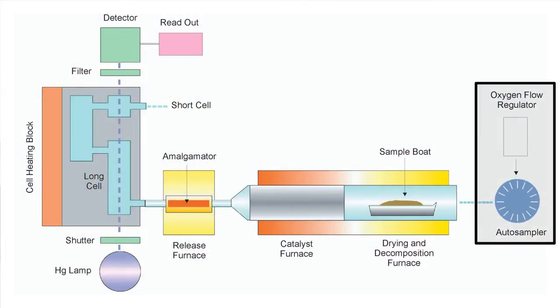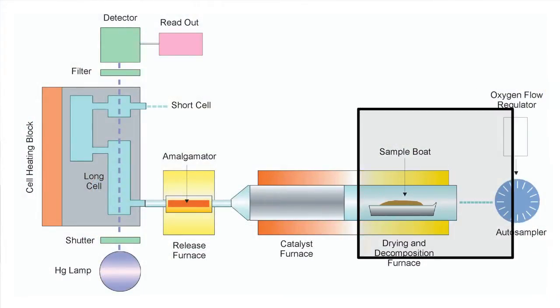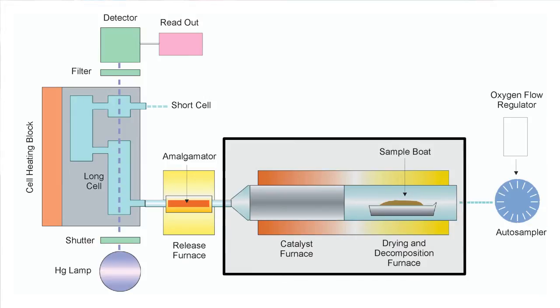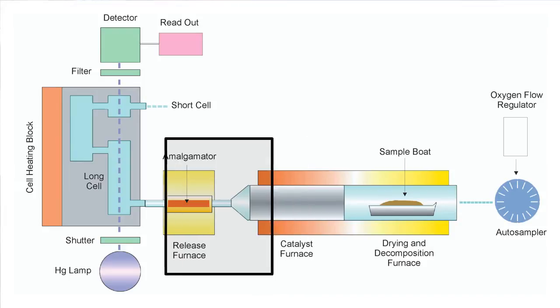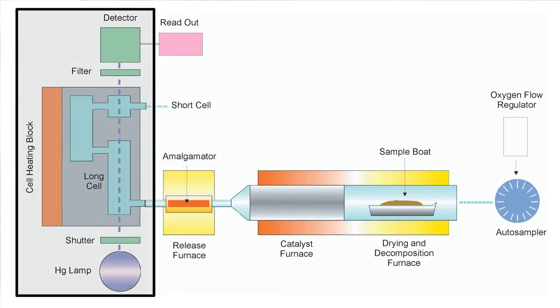The decomposition products are carried with oxygen through a catalyst bed where interferences are removed and all species of mercury are reduced to elemental mercury. Mercury is trapped onto a gold amalgamator and upon heating travels through a single beam atomic absorption spectrophotometer for measurement.